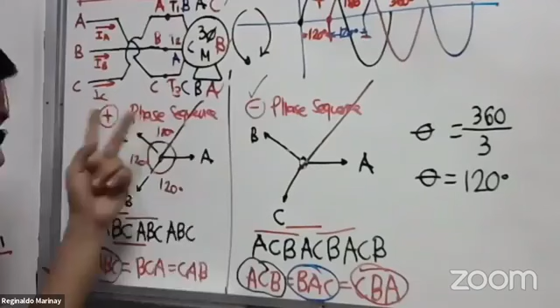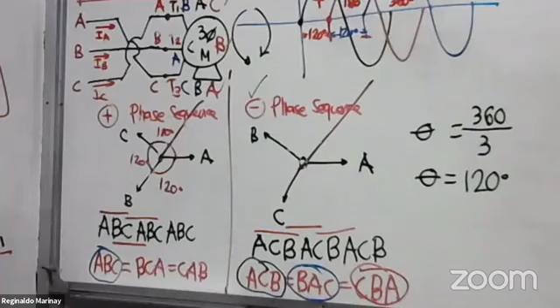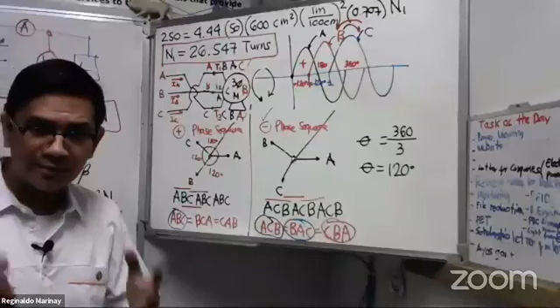So that is the effect of phase sequence on motor rotation. When you change from positive to negative, or negative to positive, vice versa, you are changing the phase sequence. Phase sequence is very important in rotating machinery - it's very important, it affects the rotation.